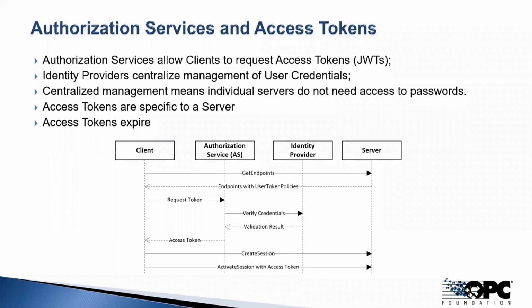Specific points about these access tokens, they are specific to a server, and this is by design, because one of the problems with username passwords, once you've got that password, you can use it anywhere and any way you want, and that's a huge security flaw. So when you're dealing with access tokens, if you want to connect to one PLC, you need an access token for that one. You want to connect to a different PLC, you need a different access token. And of course, access tokens expire, which means you have to be constantly renewing them, which is a necessary security feature. It requires a little bit extra logic. But the benefits, once you have all of this stuff in place, in terms of centrally managing your user identities and your access control, is going to be simply too large to ignore for most installations.